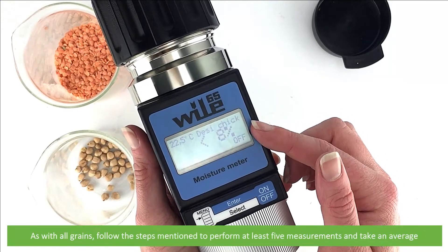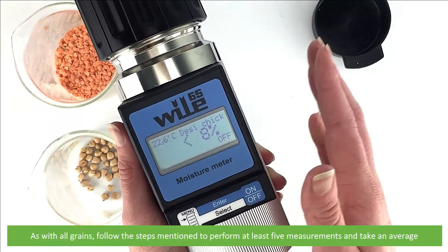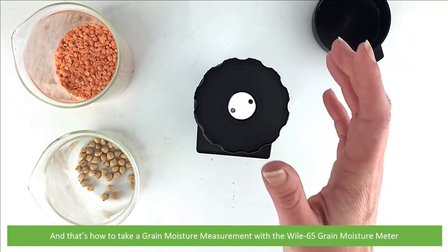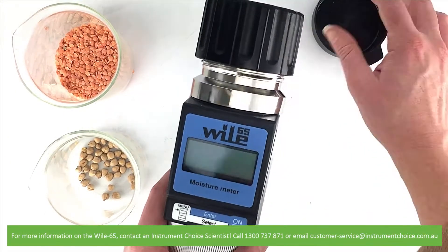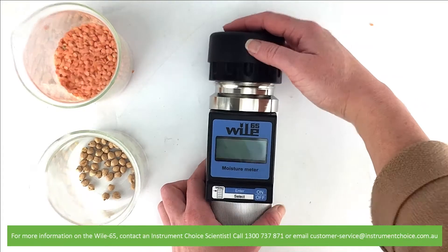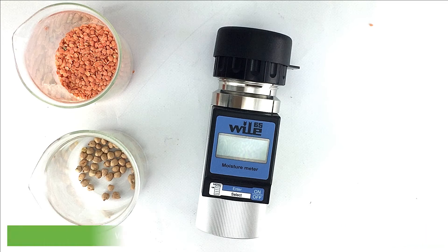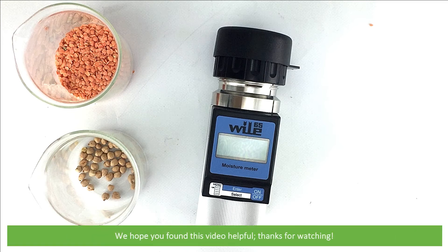As with all grains, follow the steps mentioned to perform at least five measurements and take an average. And that's how to take a grain moisture measurement with the Wile 65 grain moisture meter. For more information on the Wile 65, contact an Instrument Choice scientist. Call 1300 737 871 or email customer-service at instrumentchoice.com.au. We hope that you found this video helpful. Thanks for watching!